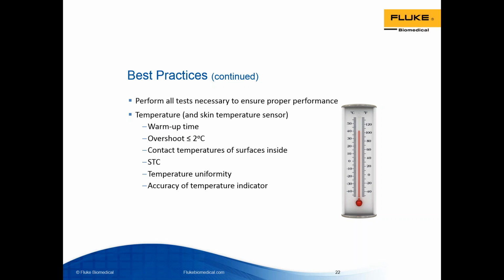Make sure of the accuracy of the temperature indicator and make sure the temperature control sets the temperature to the correct value. And finally, lastly, measure the skin temperature sensor with a calibrated heater assembly. So test to ensure the temperature control matches the actual temperature sensed by the skin temperature probe. Because remember, the skin temperature probe is taped onto the skin of the baby, and that lets the incubator know what the infant's temperature is, and if it's too hot or too cold, the incubator will automatically change the temperature to adjust and hopefully help that patient.